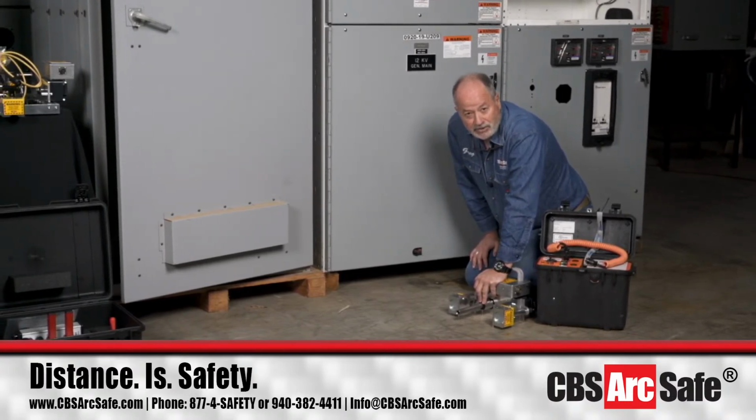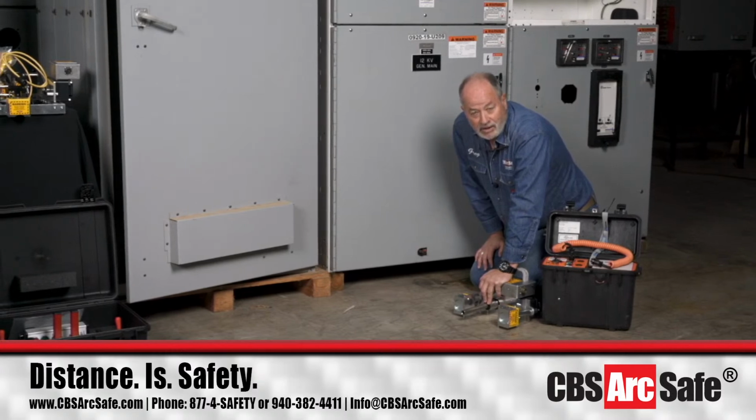If you haven't racked breakers in a long time at a facility, you may find yourself having to manually turn the racking mechanism maybe a quarter of a turn to break it loose. And I'll give you an example I ran up in Alaska in a substation with Westinghouse DHP breakers. They hadn't racked a circuit breaker in 9 years, and I went up there to help train people. It took 27 foot-pounds to get this particular DHP breaker in and out with our RS1. When we went to the hydroelectric facility inside of a mountain using the same size breaker, the DHP values were much closer to normal, which was down at 17 and 15. 17 for move, 15 for install.